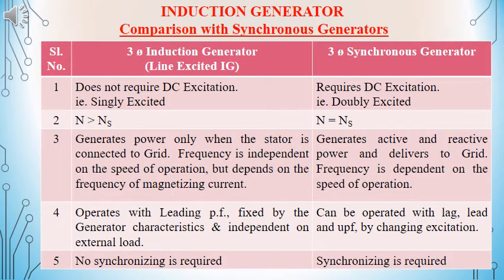We will now compare between the synchronous generator and the induction generator. In the case of induction generator, we do not have any DC excitation required and it is a singly excited machine. But for synchronous generator, there should be a DC excitation and it is called a doubly excited machine. For induction generator, the speed of operation will always be greater than the synchronous speed, but in the case of synchronous generator, the speed of operation should be the synchronous speed itself.